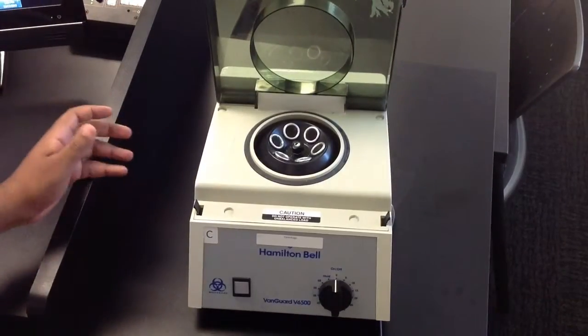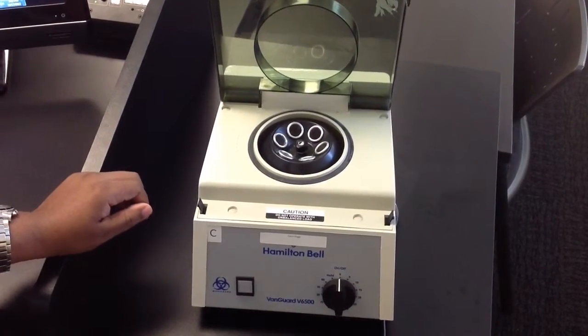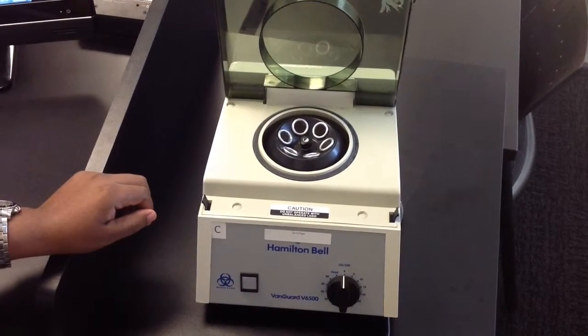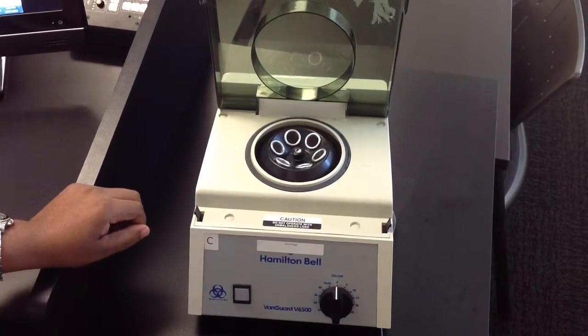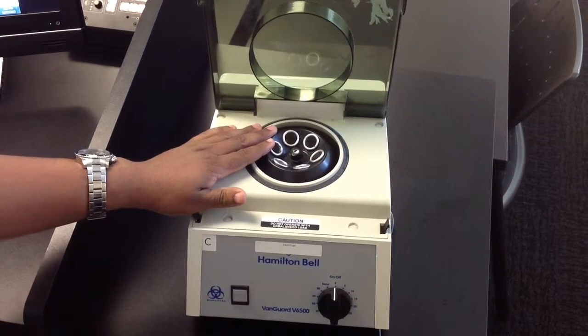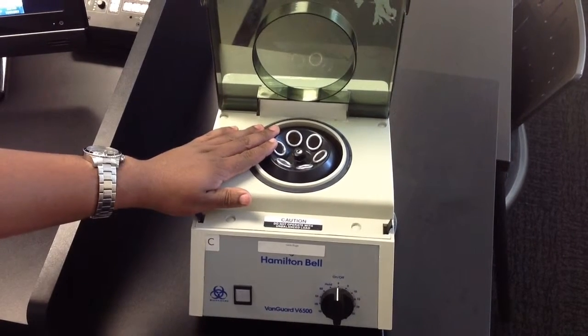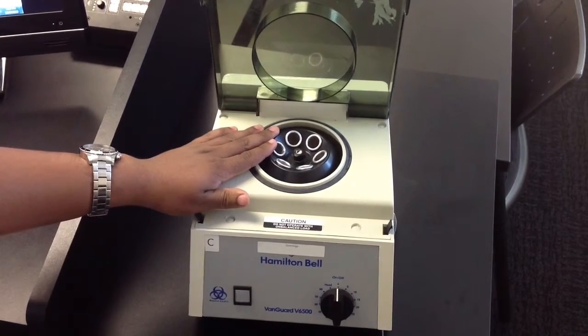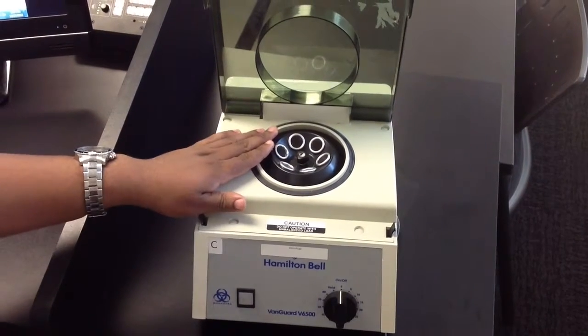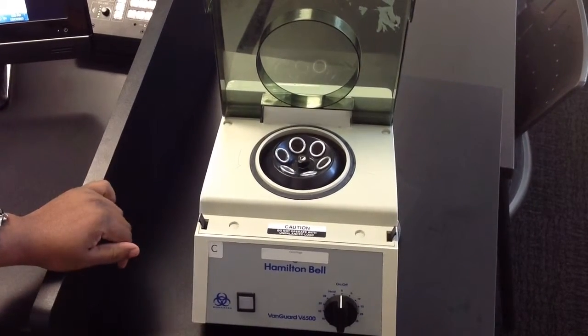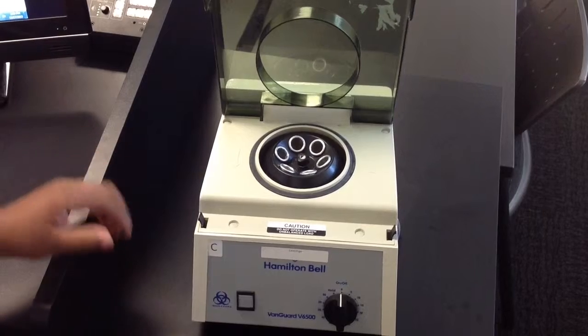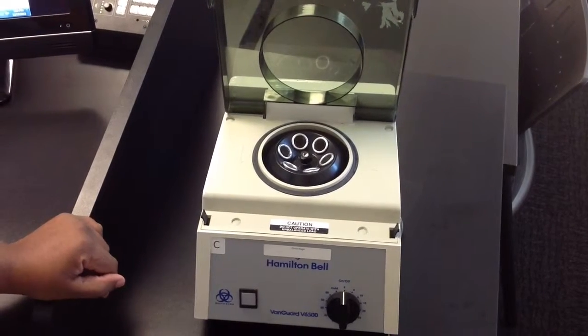Now, the speed of the centrifuge is based on what type of centrifuge it is. We have low speed, high speed, and ultra centrifuges. This particular model here is a low speed centrifuge, which normally gets up to about 9,000 rpm.